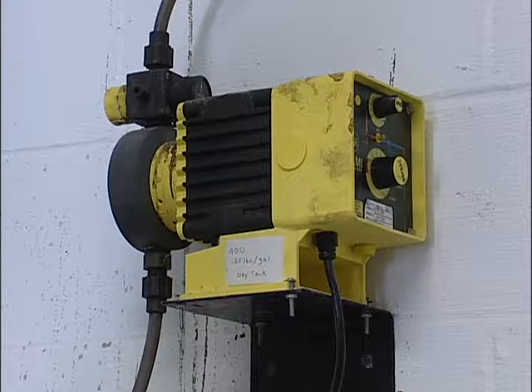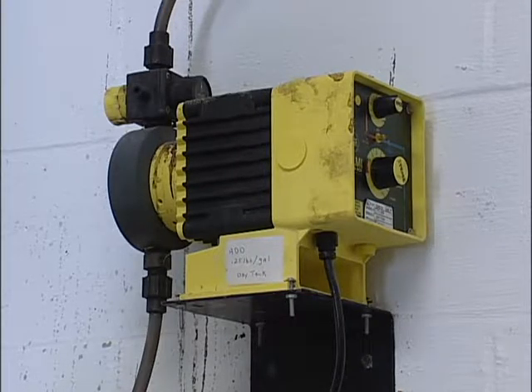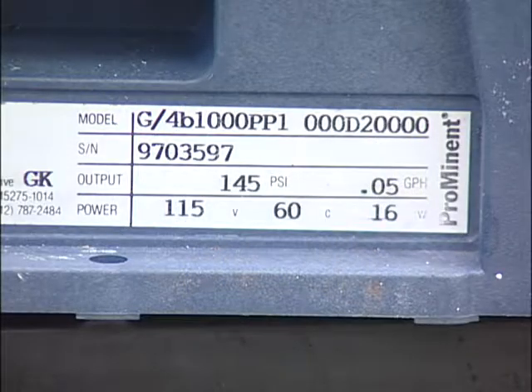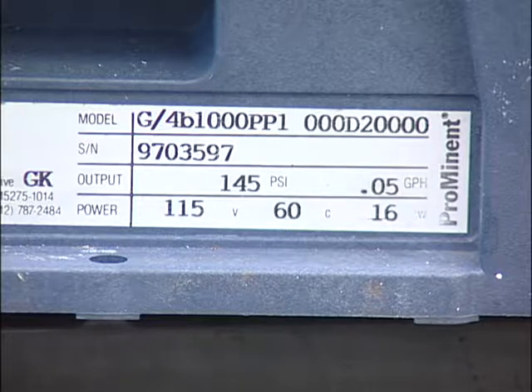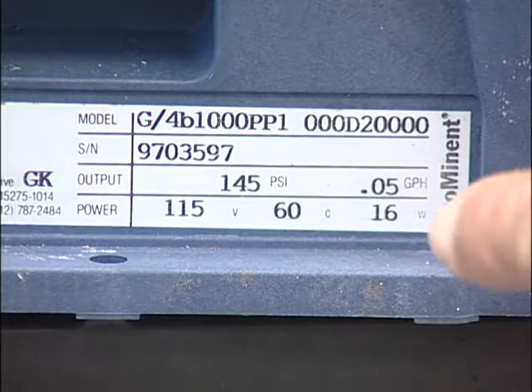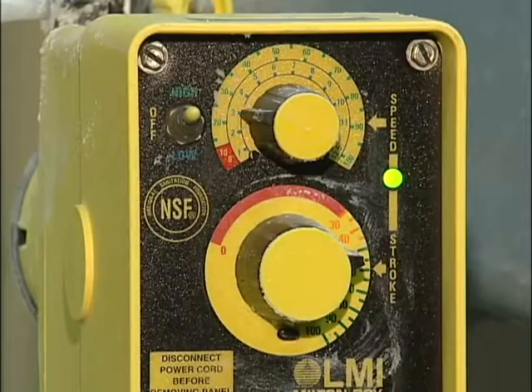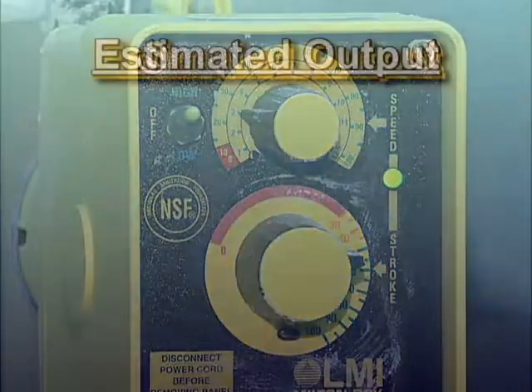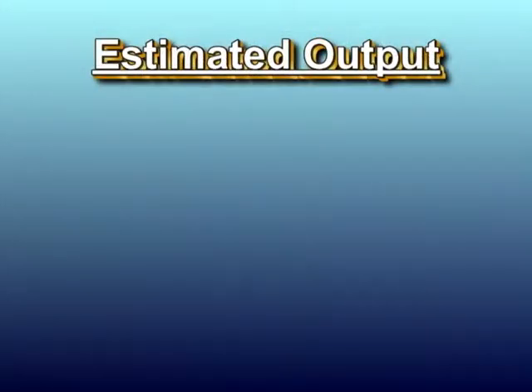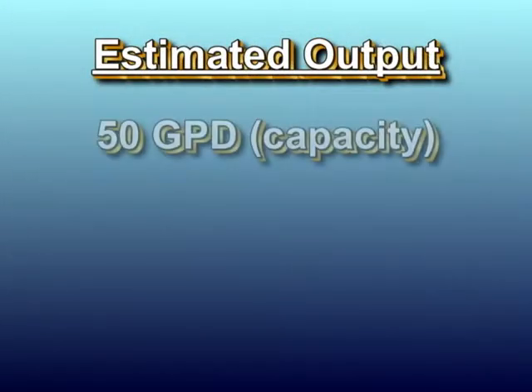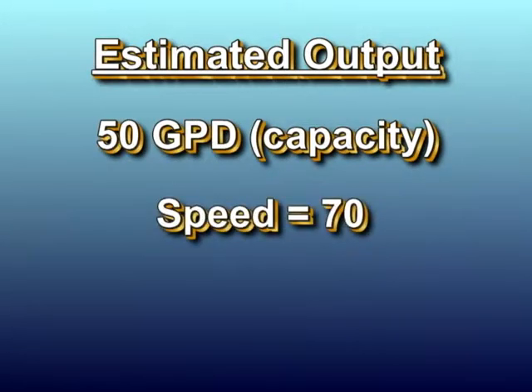Assuming that you have purchased the right pump for the job does not mean you can just plug it in and watch it work. Some pump manufacturers suggest that the output of a pump can be estimated by multiplying the rated capacity of the pump by the speed setting and the stroke setting. For example, if a pump is rated at 50 gallons per day maximum and the speed is set at 70 percent and the stroke is set at 75 percent...